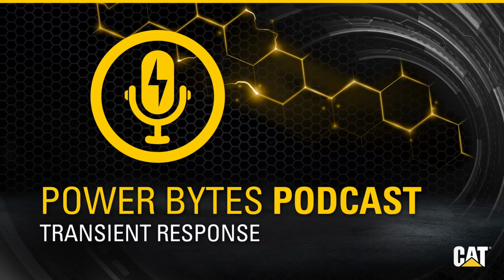If the load on the generator increases, the speed of the generator slows down. This impacts the frequency and the voltage of the generator, causing them to dip. If the load decreases suddenly, the speed of the generator is likely to increase. This will cause the generator to overshoot. The measure of how large the dip or the overshoot is, and the time it takes for the generator to return to its steady state operation, is what's typically considered the transient response of the generator.